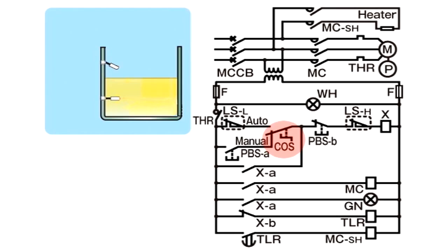If C-O-S is set to auto mode, X is excited and returns to sequence operation. With X-A turned on, current begins to flow from X-A to P-B-S-B, L-S-H, and to X, enabling X to remain excited. By repeating this operation, the level in the tank is controlled within the preset parameters. However, if C-O-S remains in manual mode, the pump does not operate because X is not excited even though the L-S-L relay is turned on. The tank eventually becomes empty.